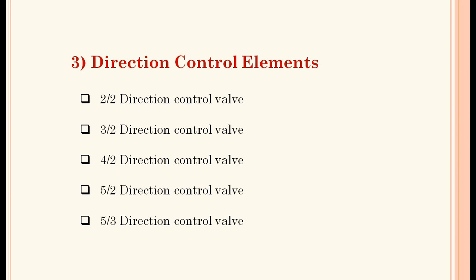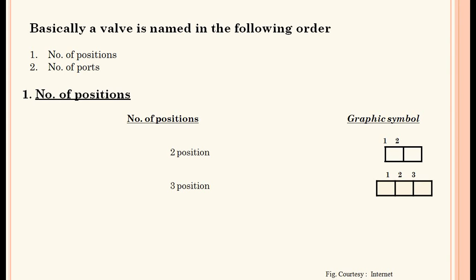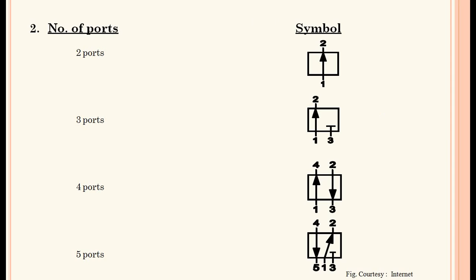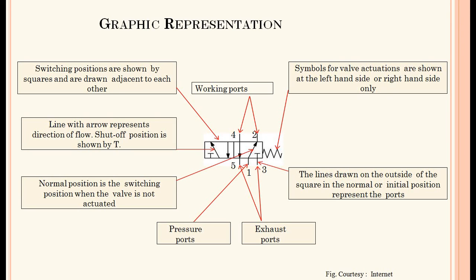Direction control elements — the third group — include 2/2, 3/2, 4/2, 5/2, and 5/3 direction control valves. A valve is named in the following order: number of positions and number of ports. Two or three positions are possible. Number of ports: two ports, three ports, four ports, and five ports. How the direction control valve is represented — with exhaust ports, pressure ports, working ports, and the switching lines — is shown in this slide.